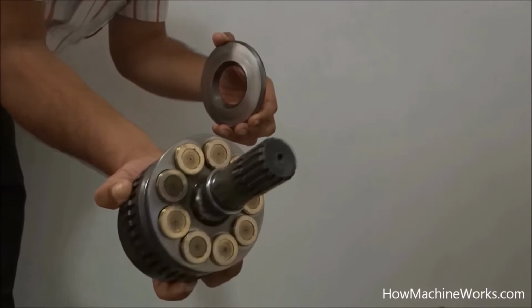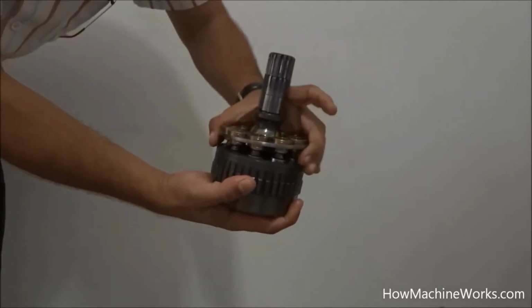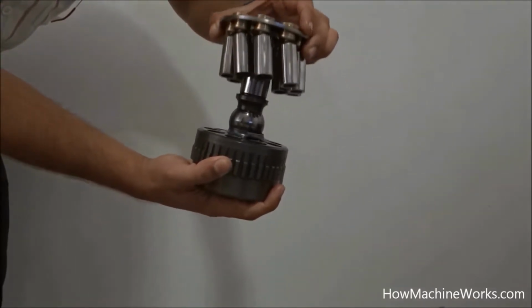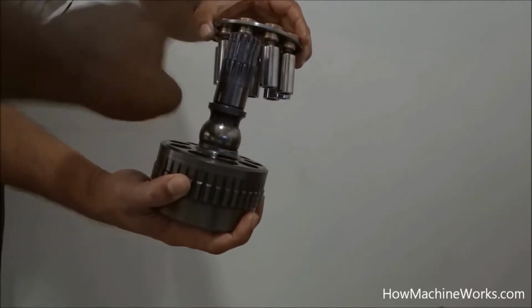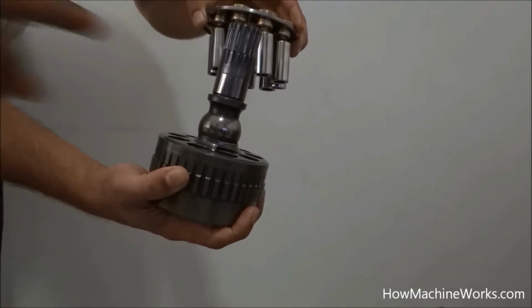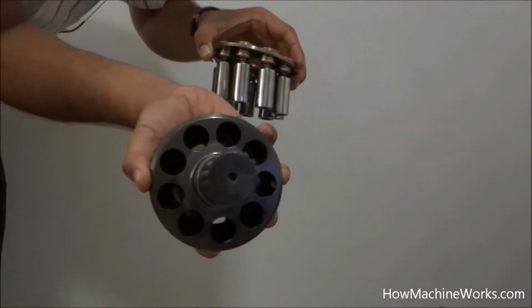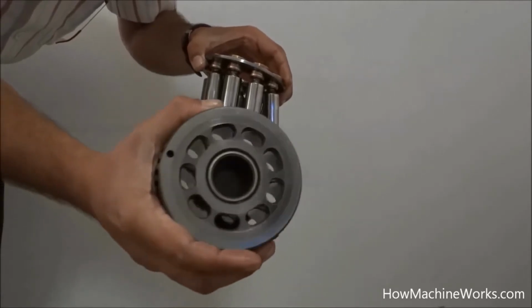So I already showed the rear view over there, and that's actually resting on the swash plate. Now let's remove the pistons outside. So those are the pistons being taken out, and the o-ring has gone down, I think. Okay, we have the pistons over there. We have many pistons which are inserted into the drilled holes inside the cylinder. You can see the shaft and the cylinder is a single piece over there. The drive shaft is directly connected to the cylinder at that section. Now you can see the pistons which I have shown, and these are the holes where the pistons will actually be inserted, right?